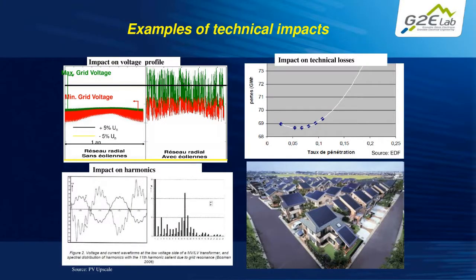Besides this variability, you also have the technical impact on the distribution grid. I won't detail this since it's more technical, but you have voltage challenges, voltage impact on the grid, technical losses on the grid, and also harmonics at the secondary distribution level, because some transformers have seen a lot of failures due to harmonics caused by low quality inverters. We have solutions, we know how to deal with harmonics, but the question again is accommodating the fast evolution, determining where, and who's going to pay for the initial investment.